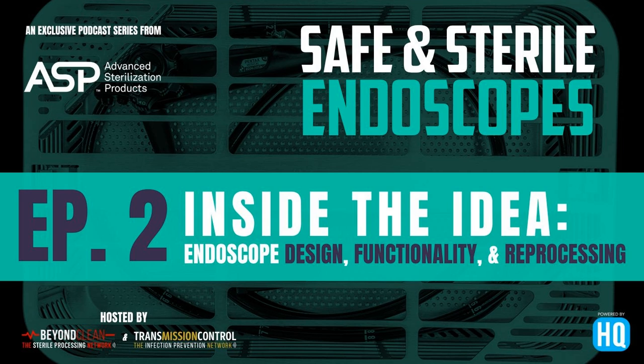So as we continue to move from AERs, ECRs, and now into, okay, now we want a sterile scope. What does that look like? Can we even sterilize something that's 6 to 9 feet long? Can we guarantee that those internal lumens are cleaned properly? Because if you look at that change in reprocessing and that standard, are we going to high level disinfect and then send it for sterilization? Or are we going to manually clean and then prep it for sterilization so that it's not going through the HLD part of the process? And that's where we'll rely on the IFUs from the devices as they come to market to see what that is going to look like.